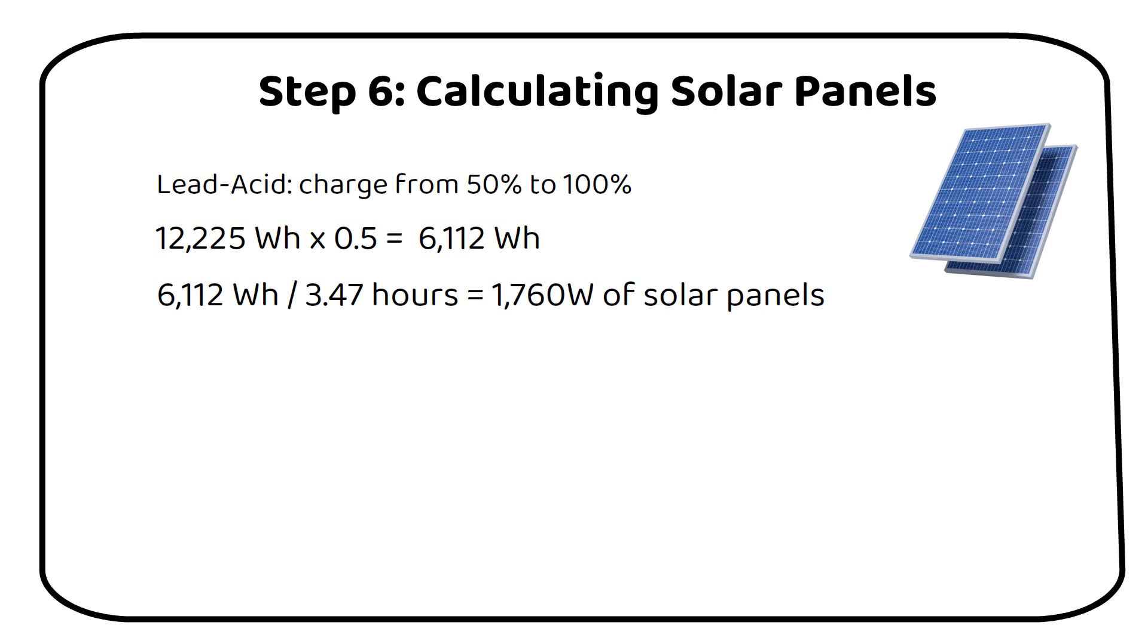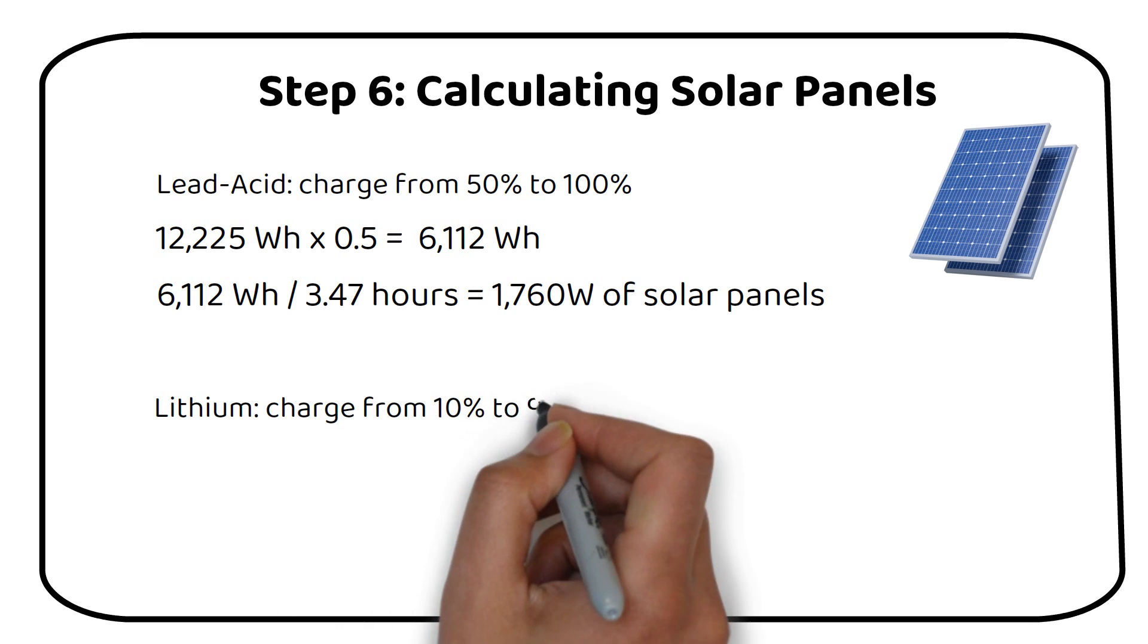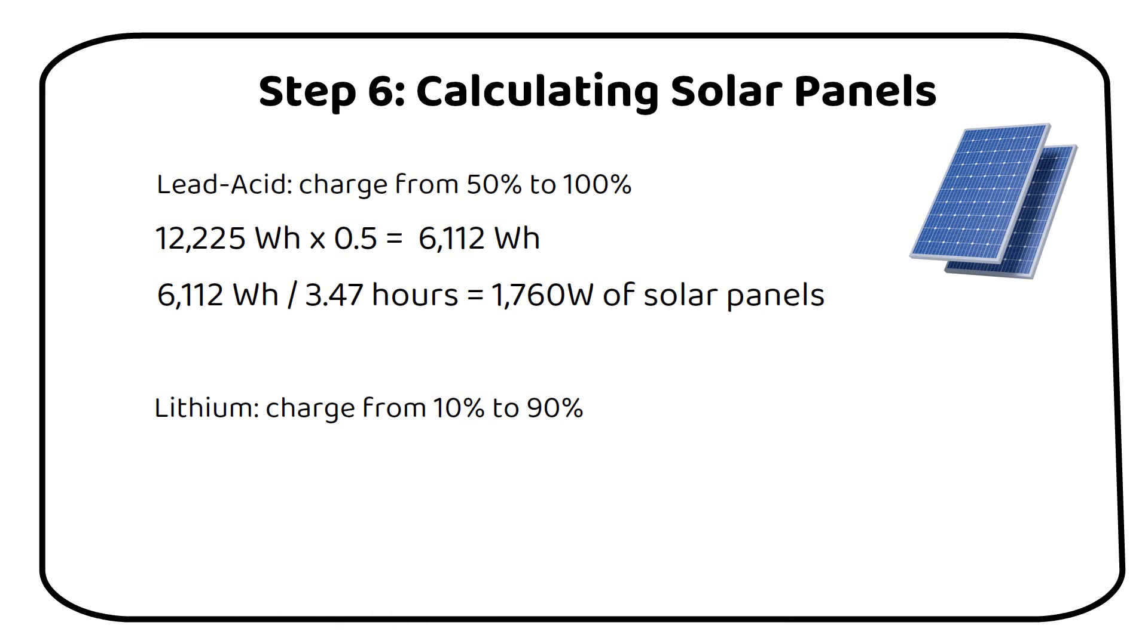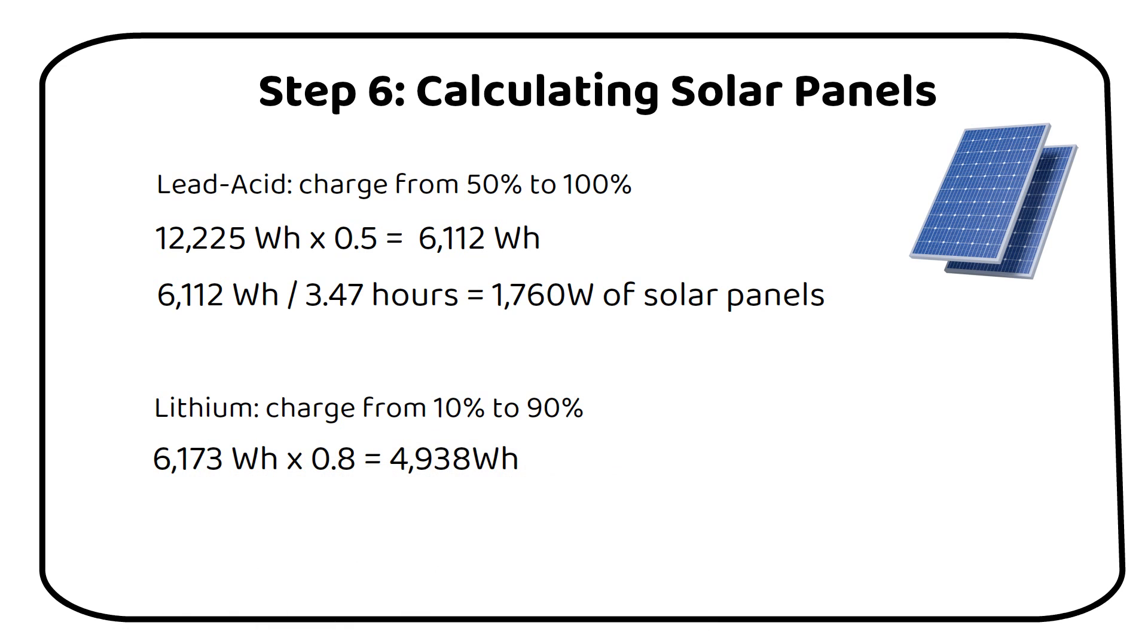For lithium batteries, the calculation is slightly different. Considering you can use 80% of lithium's battery capacity, let's say you need to recharge from 10% to 90% using the same total capacity of 6,173 Wh. You will need to recharge 4,938 Wh in a day. Again, divide this by the sun hours. 4,938 Wh divided by 3.47 hours equals 1,420W. So for a lithium battery, you will need about 1,420W of solar panels to ensure a full day's recharge during winter.